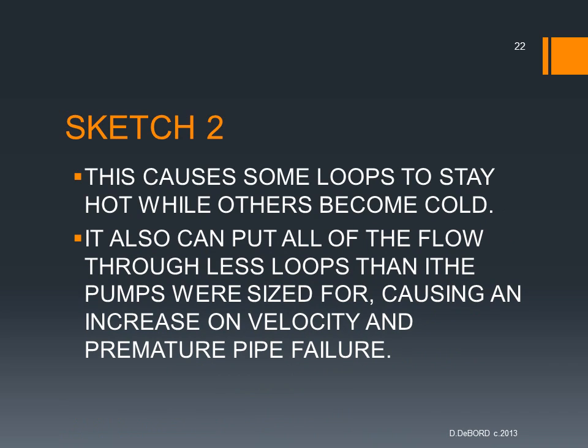What happens then? It causes some of the loops to stay hot while others become cold. You can also put all the flow through fewer loops than what the pumps were sized for, and what happens then, we cause an increase in velocity and we have premature pipe failure because the water is circulating very quickly through one loop and not getting to the other loops. So we exceeded our 3 feet per second, which is the limitation that I use for hot water recirculating because it's always moving, it's hot, it has air entrained in it, it's erosive.